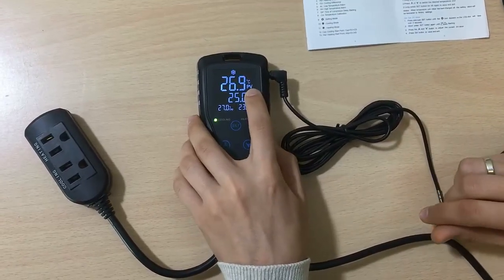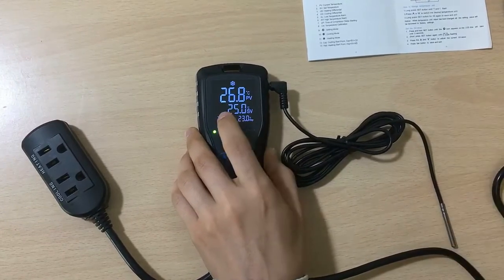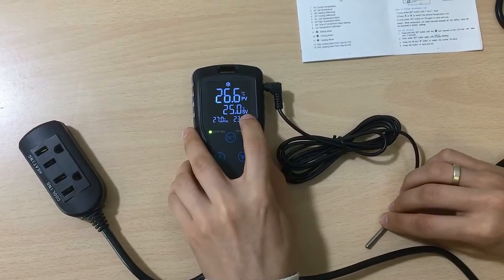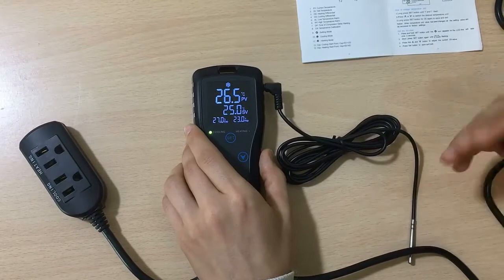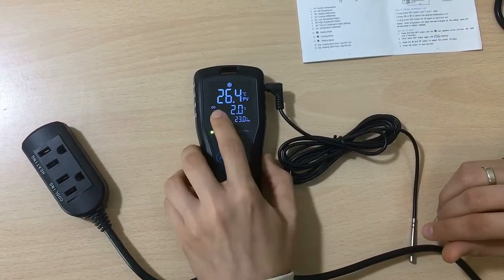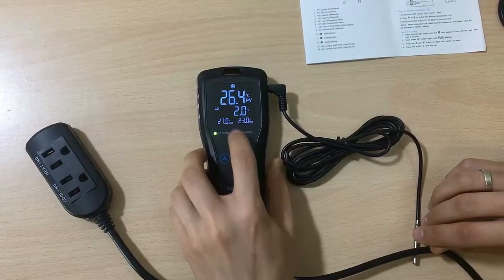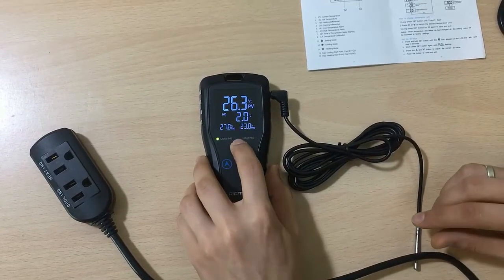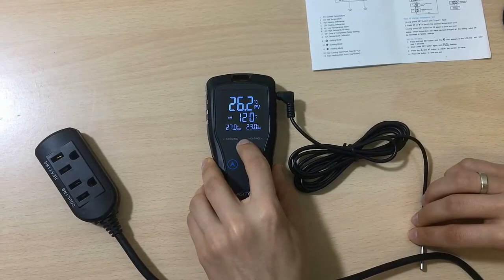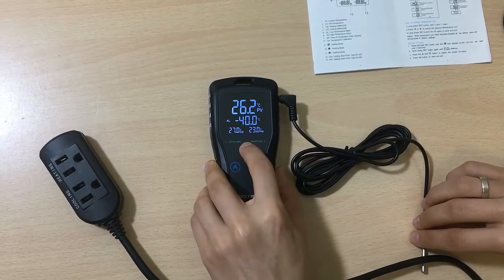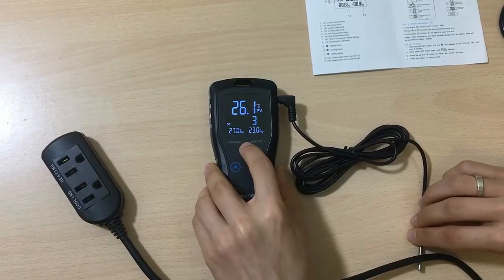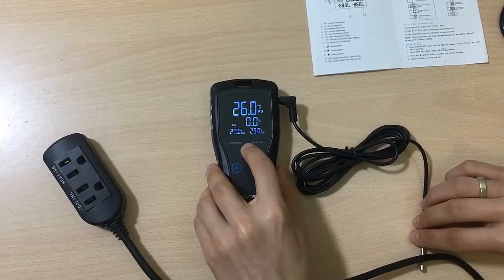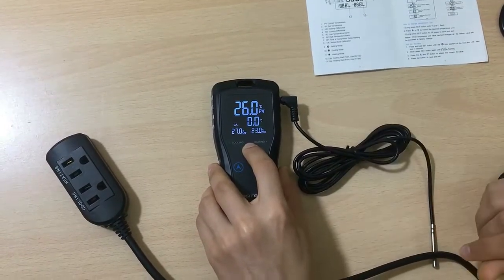For example, the PV displays the current temperature shown at the sensor. The SV is the set temperature which you want to set. CD is cooling differential, and HD is heating differential. AH is high temperature alarm and AL is low temperature alarm. The DP is the time of the compressor delay starting, and CA is temperature calibration.